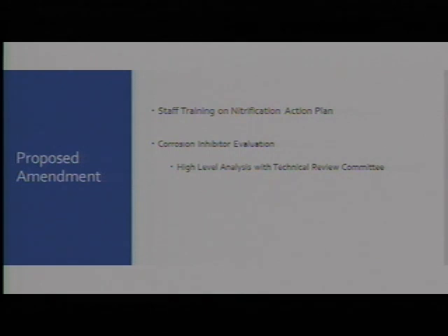Do we have enough information to make that decision now, or do we need to go to the next level, which we have, and this is an item within additional services. It's called a pipe loop test, where we'll run different scenarios, different chemical constituents through a system, see how they operate, and then determine what's best for our system. And I'll show you a picture of that here in just a second.